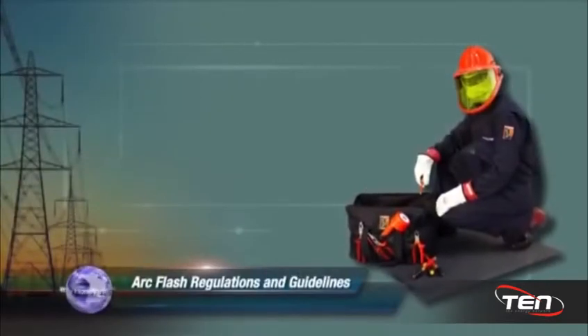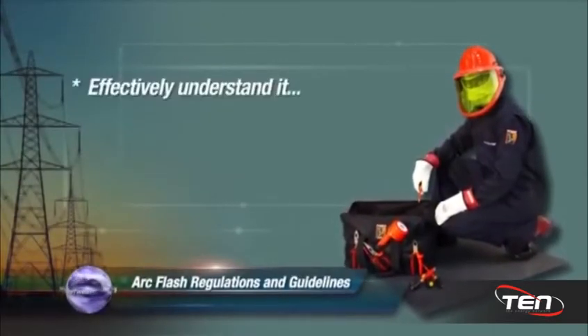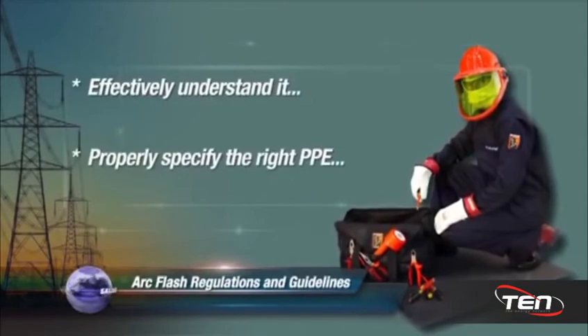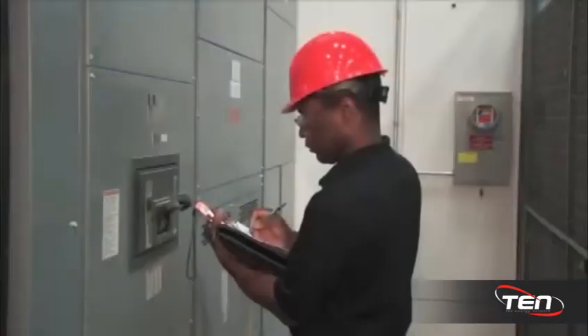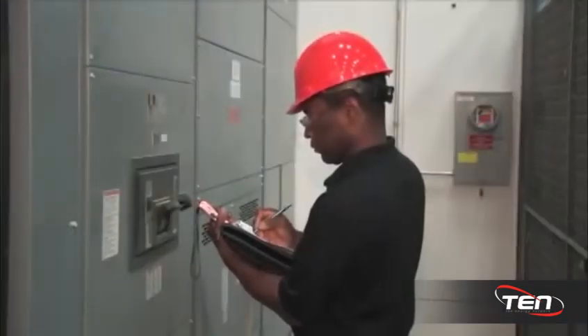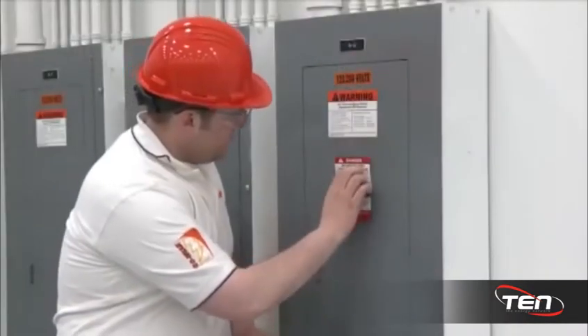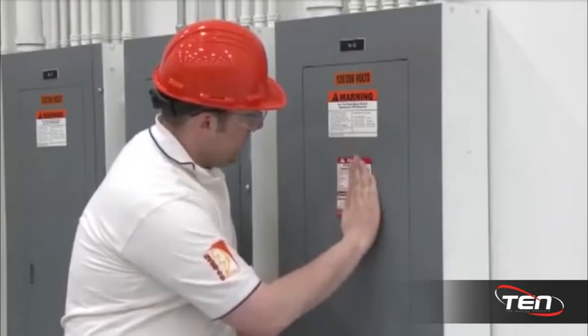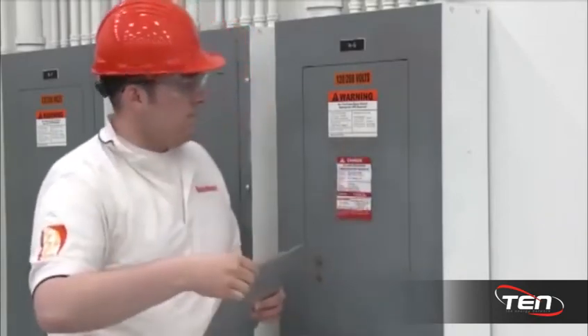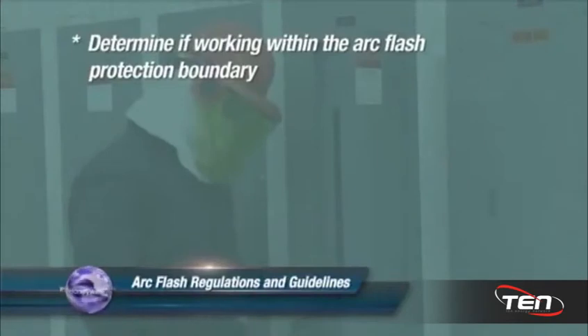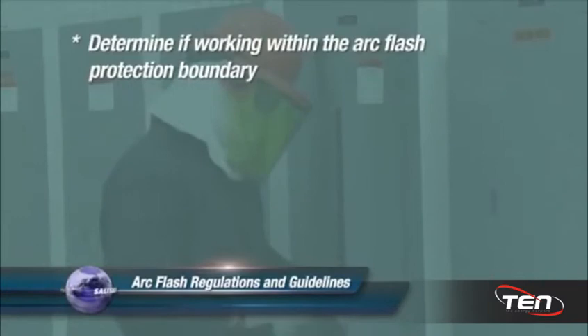One of the biggest concerns about arc flash is how to effectively understand it and properly specify the right PPE for the hazard. Ensuring your workers and your facilities are in compliance can be an overwhelming task. This video will go over some of the necessary steps so you can confidently begin to create an electrical safety program for your facility. The first step is to determine if you are working within or near the flash protection boundary. What is the arc flash boundary?